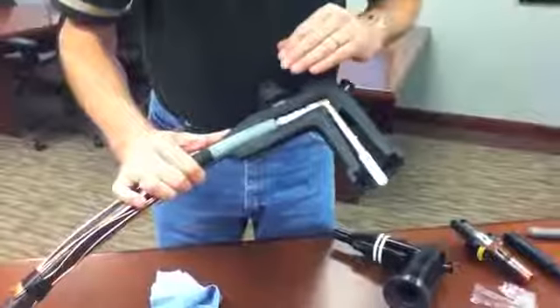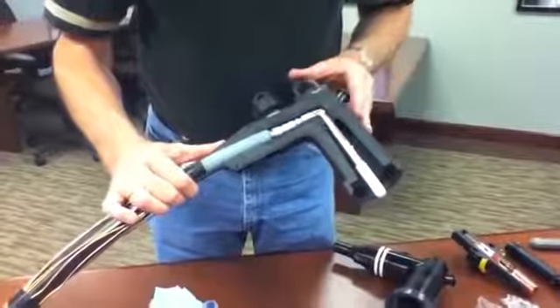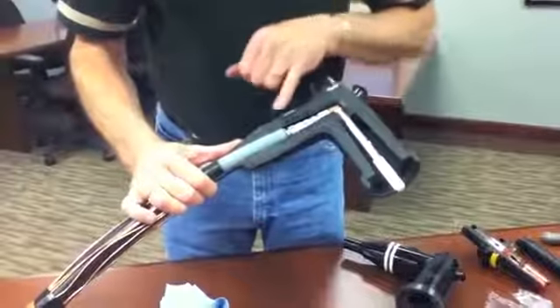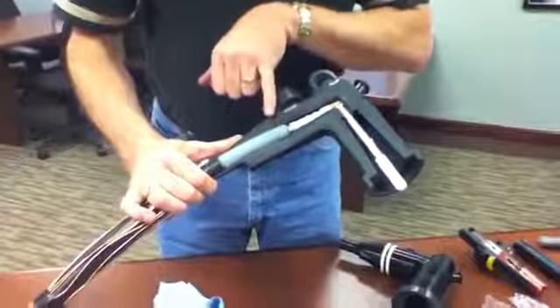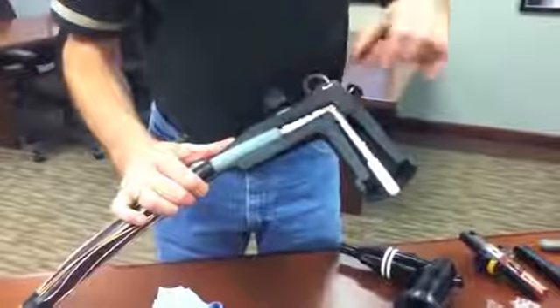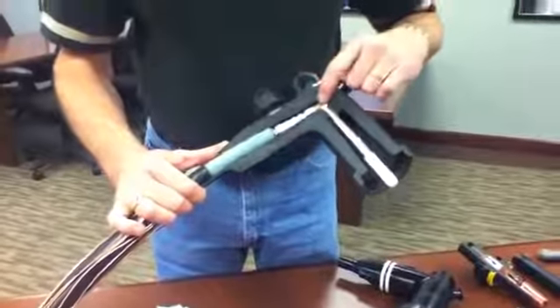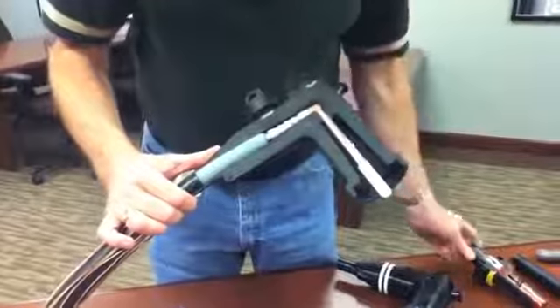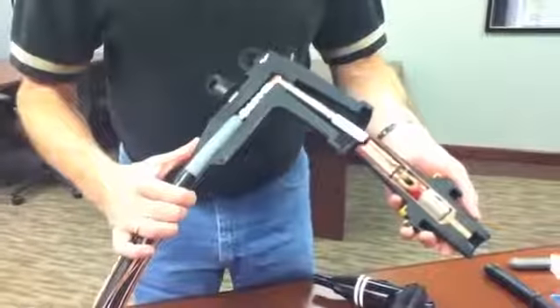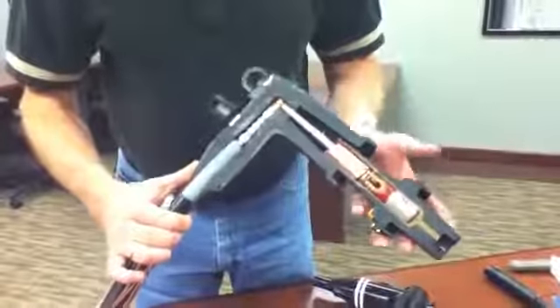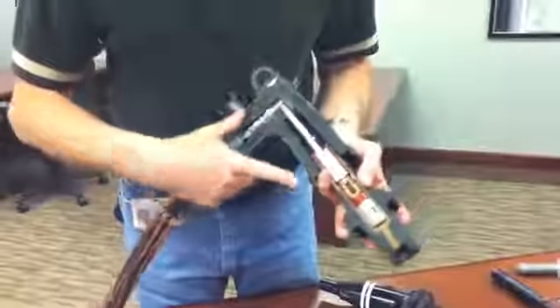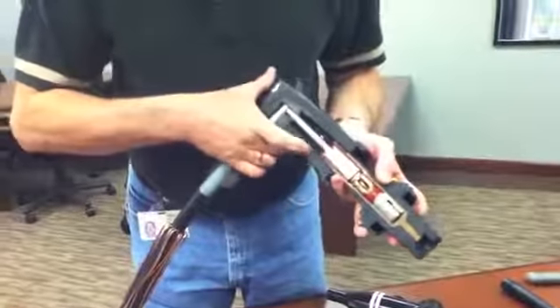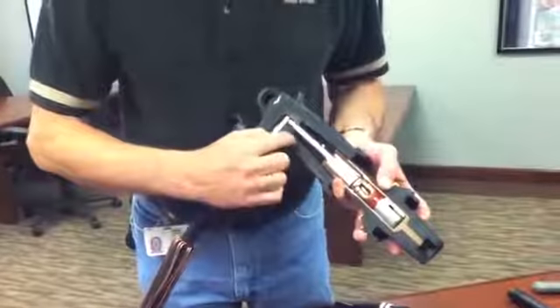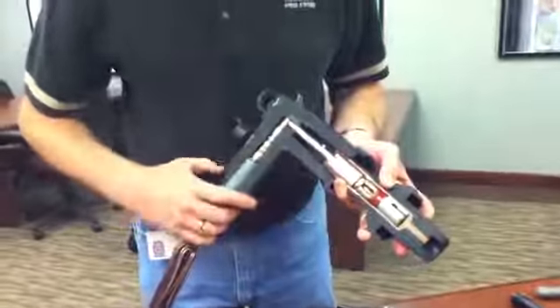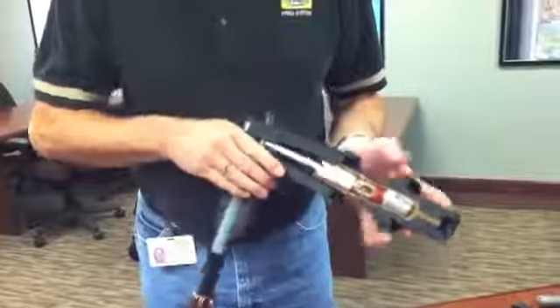Here is the assembly in the cutaway elbow so that you can see how the insulation of the cable is inside the conductive insert. The probe is aligned and properly torqued to the copper top contact. And then the last operation would be to assemble the elbow onto the bushing and then fully seat it until the locking ridge here and the locking ring there engages and locks the elbow in place.